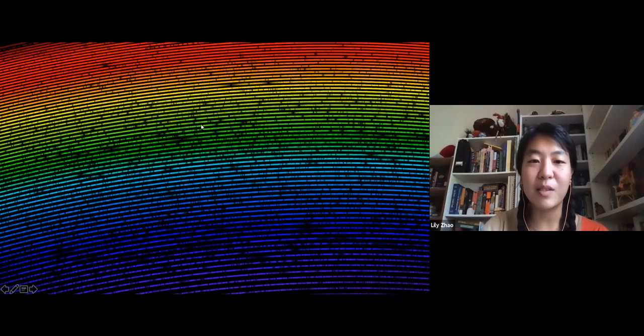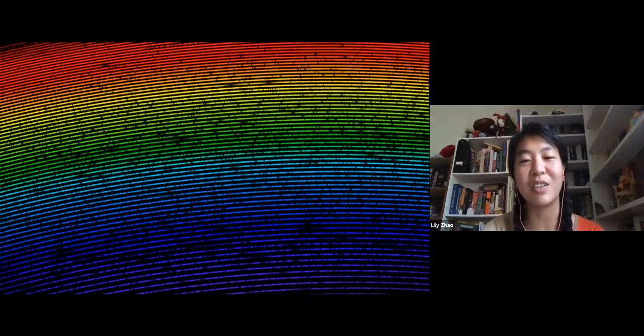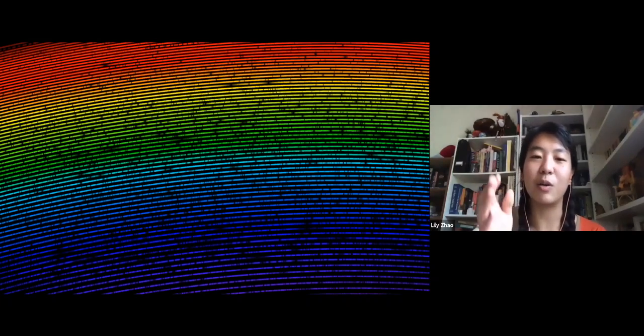The dark bands you see across each order are actual spectral absorption lines. You'll notice that they're very vertical, up and down, which is very important and something we put a lot of effort into creating. This means that all of the light hitting a row of pixels will have the same wavelength, so it won't be confused for any other neighboring wavelength, or the effects of any neighboring wavelengths.